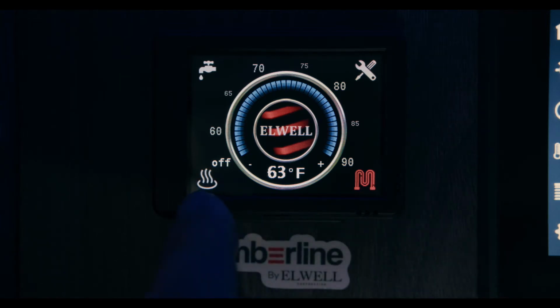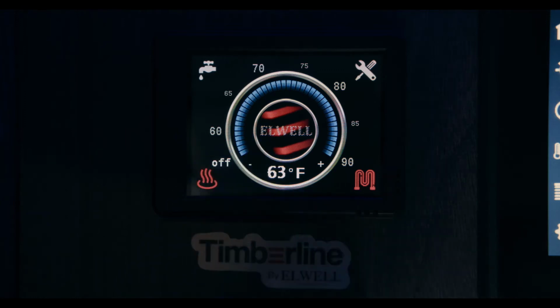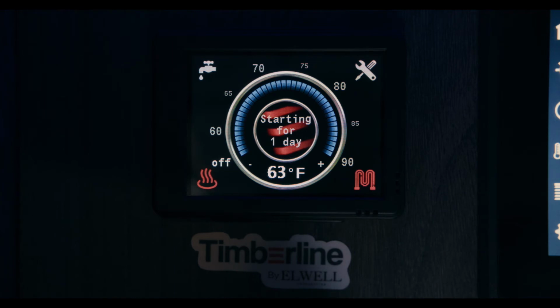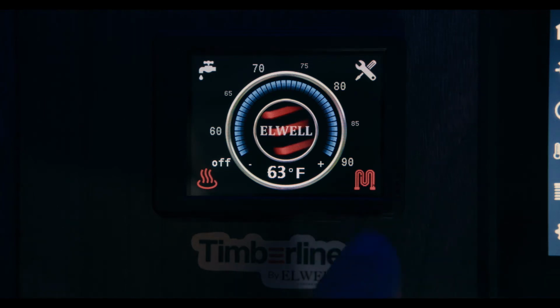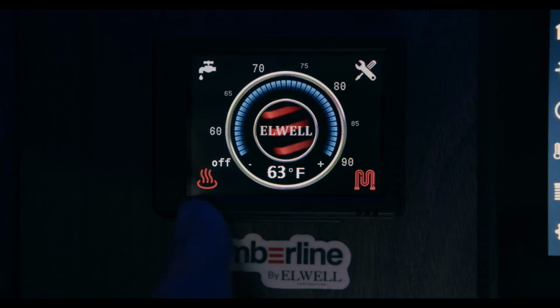The secondary heater source in this system is the fuel-fired burner on the bottom left-hand corner. This is the diesel fuel-fired burner. By initiating that heater icon, you turn on the fuel-fired burner in the system. If the electrical element cannot keep up with the demand of the heating system, the fuel-fired heater will initiate.